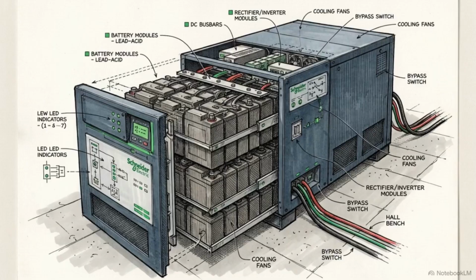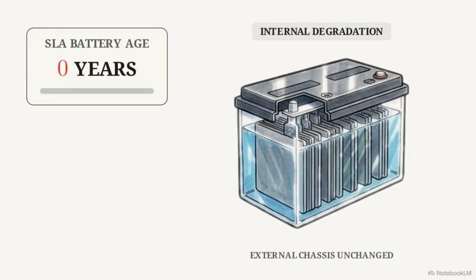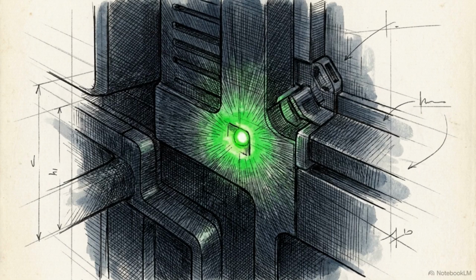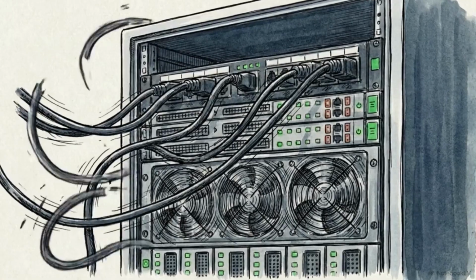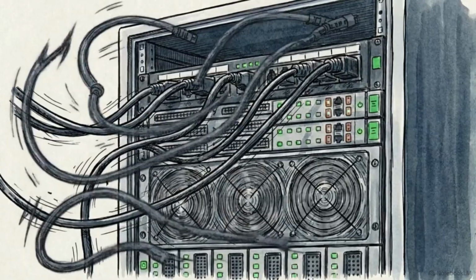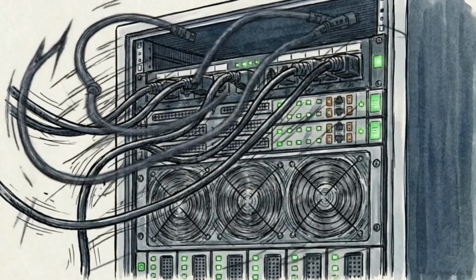crash. Underneath the chassis of almost every standard UPS is a sealed lead-acid battery. These batteries possess a predictable chemical lifespan of 3 to 5 years, and they degrade regardless of how often they are used. This leads to the green light illusion. A UPS can pass a self-test while idle because the internal resistance hasn't been challenged by a real-world load.